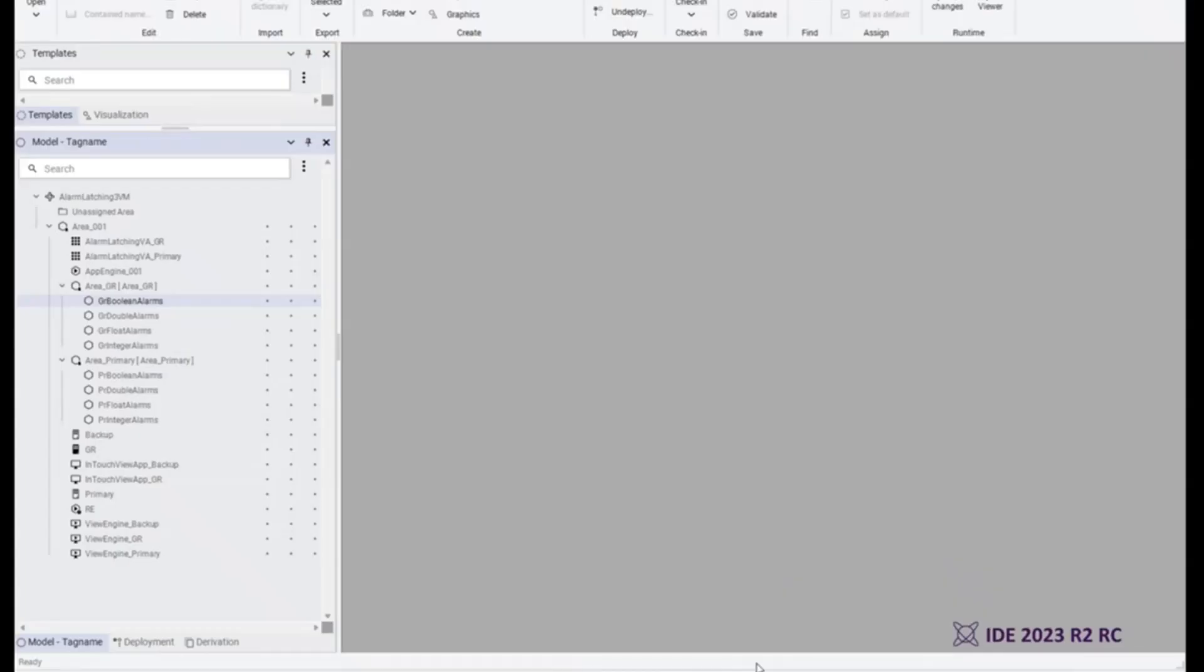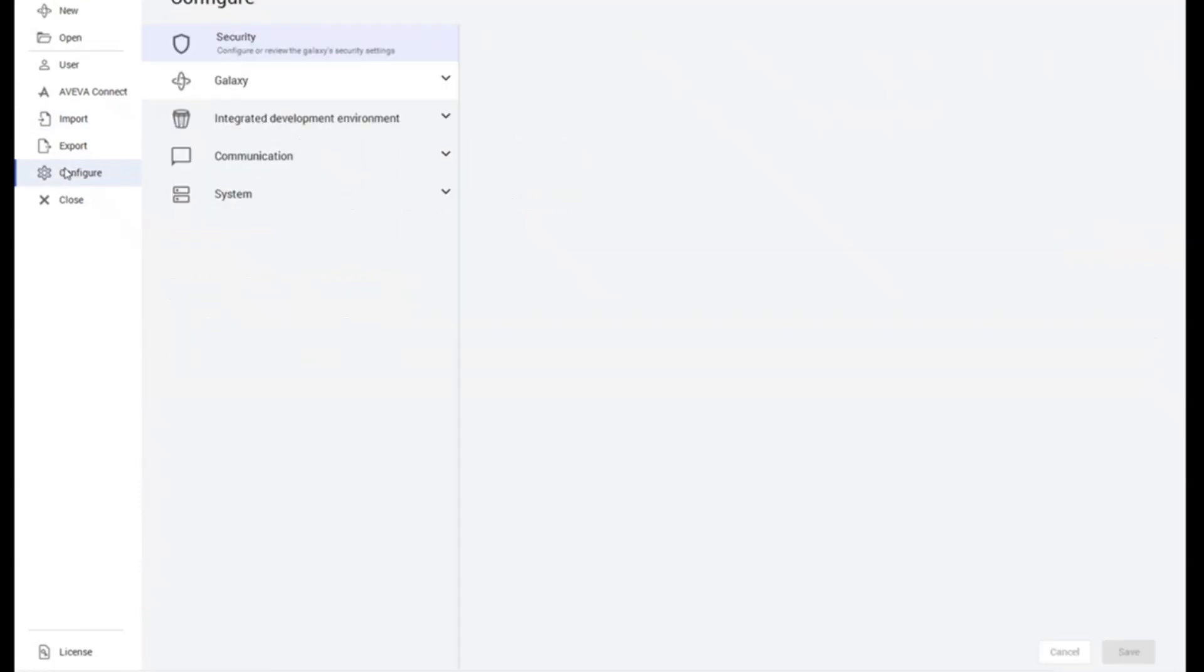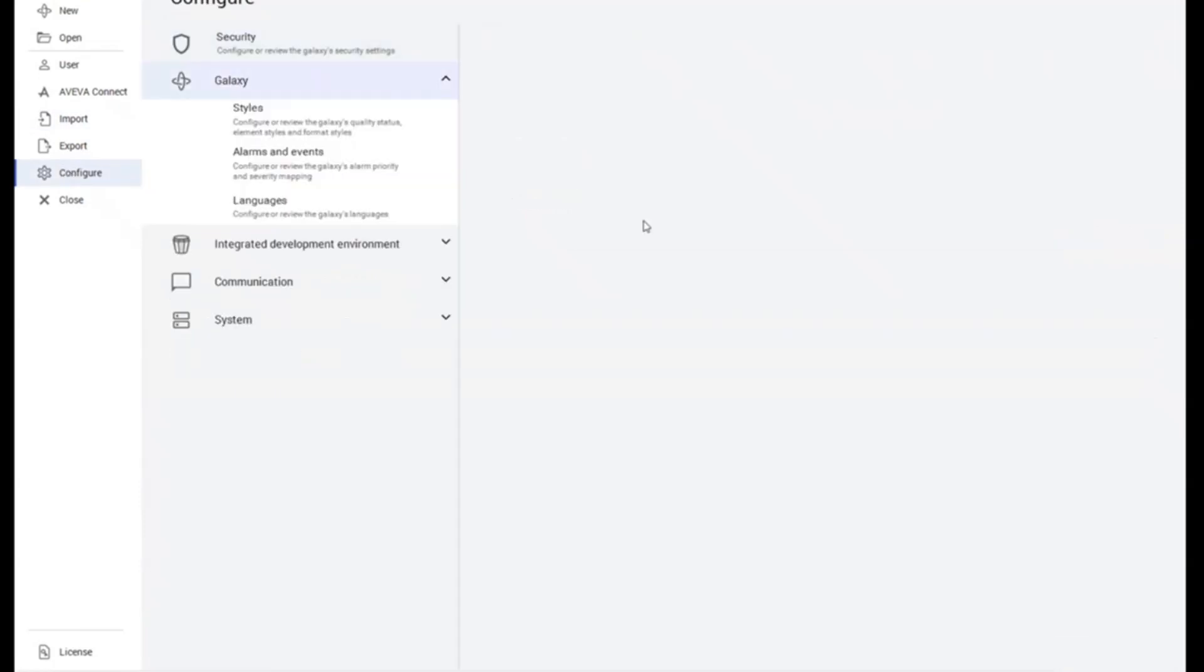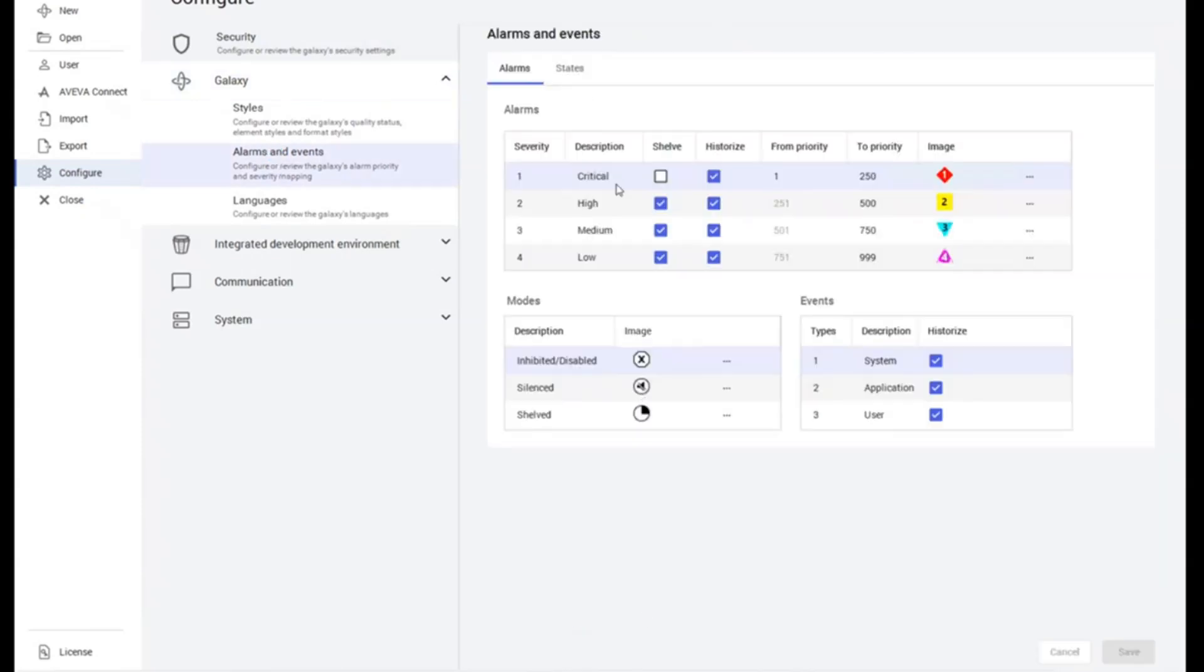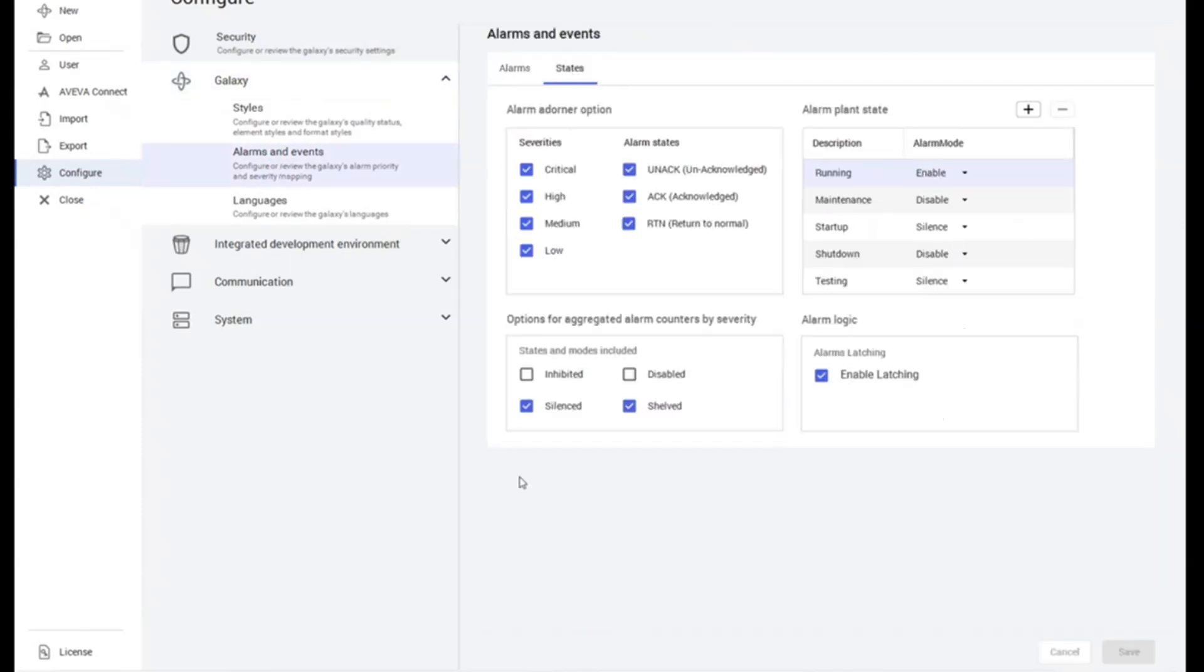That is done in IDE by clicking on the Galaxy main menu item, selecting Configure, selecting Galaxy again, clicking on Alarms and Events, and finally clicking on the States tab. You'll notice in the States tab there is a new backstage configuration item used to enable or disable alarm latching.